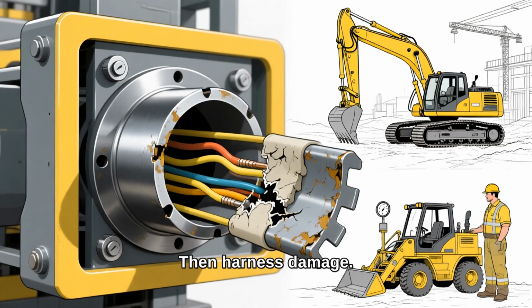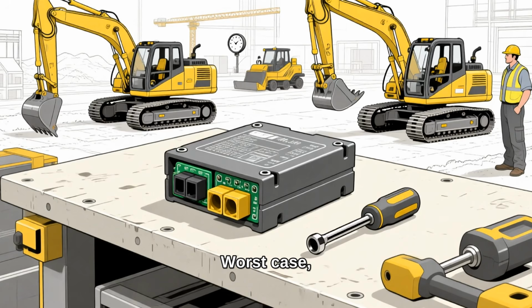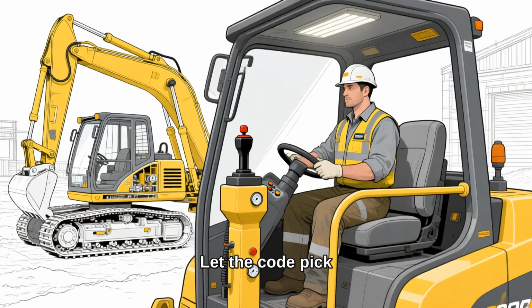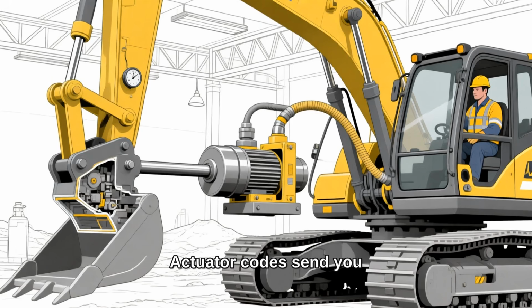Then harness damage. Chafe, a pinch point, a rub-through, or the loom crosses something sharp. That's short code country. Then the handle sensor, if the code names the handle. Then the actuator, if the code names the actuator. Worst case, the controller. It's last for a reason. It's the expensive answer, and it's usually the wrong one. So how do you isolate? Let the code pick the end. Handle code sends you to the operator side. Actuator codes send you to the machine's side. Wiring codes send you to everything running between the two.